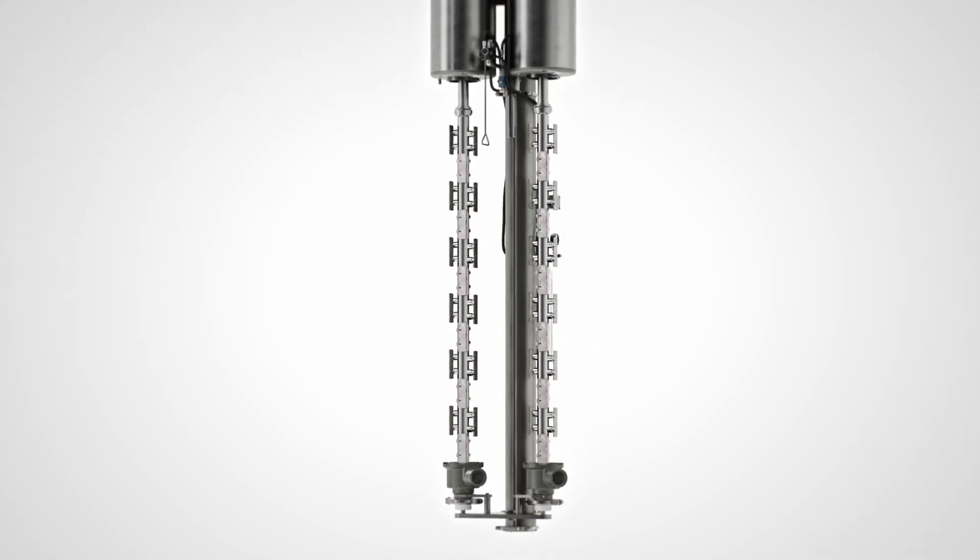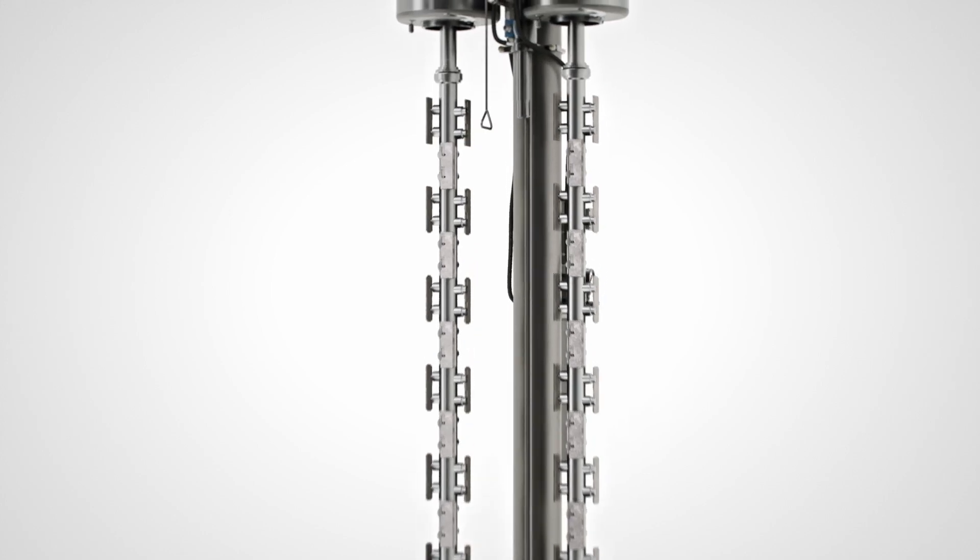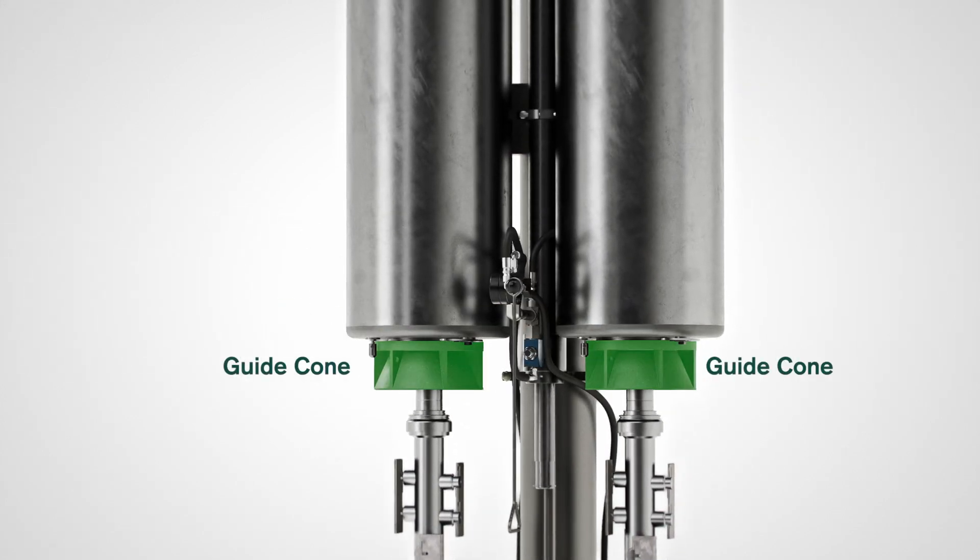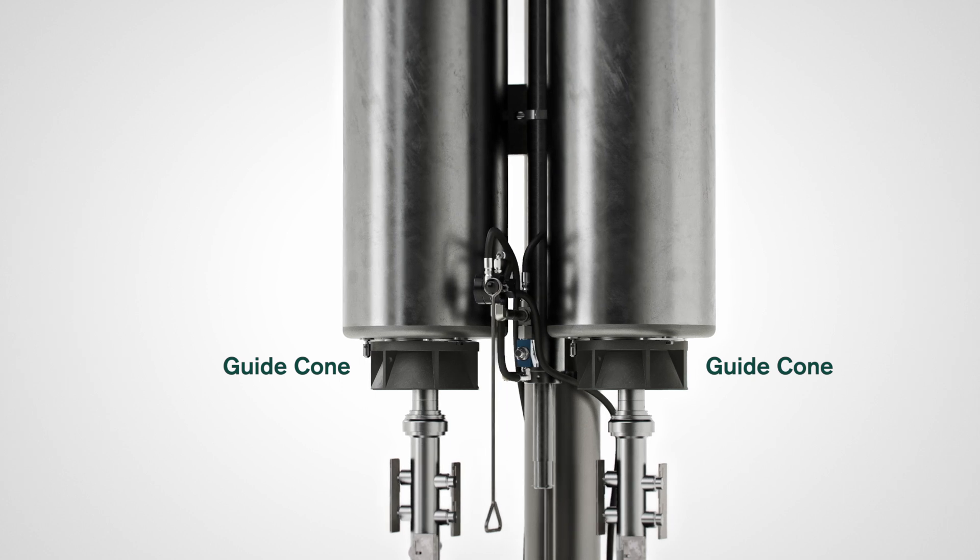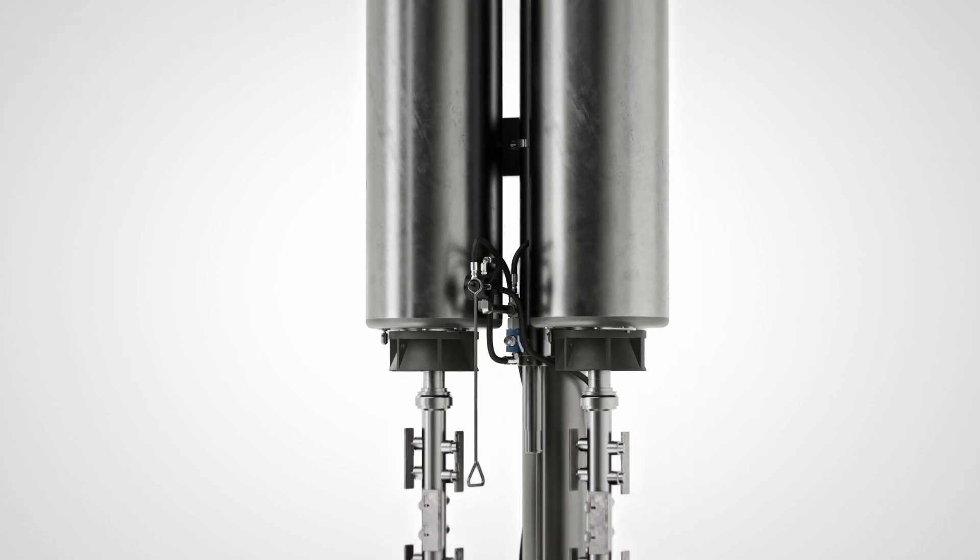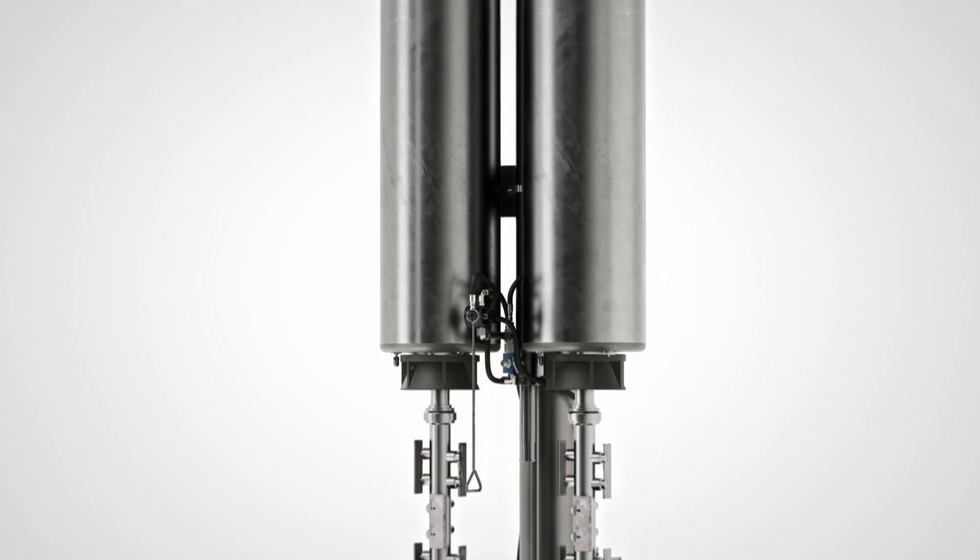Once the cleaning, inspection, or maintenance is completed, guide cones are installed for each heat exchanger to lift the mutator shafts to smoothly insert the mutator shafts and blades back into the heat exchangers.